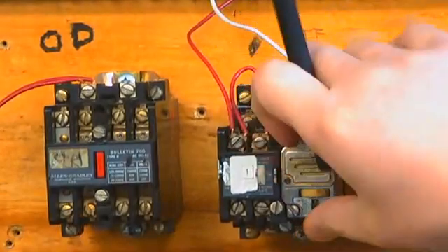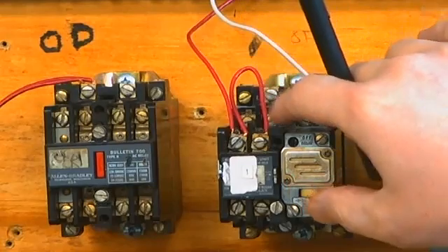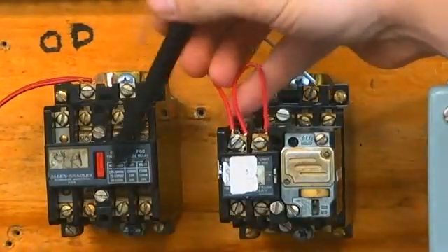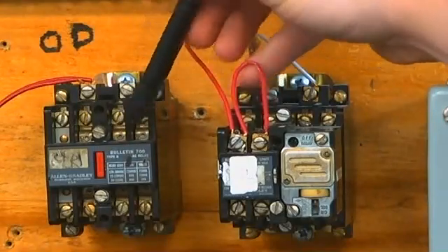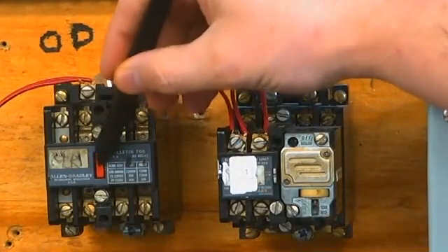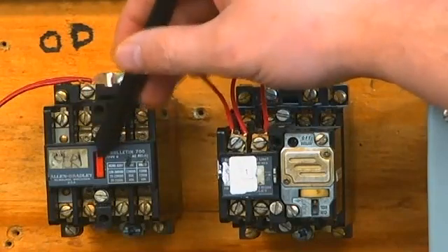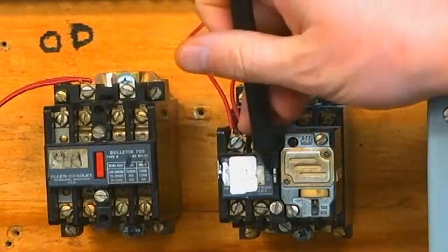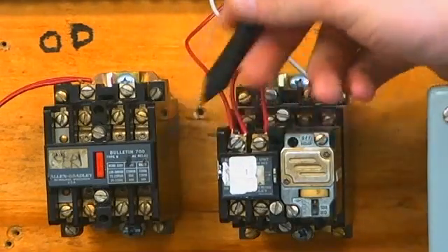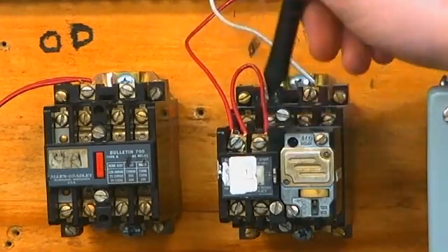I could take this thing off of here and show you that. Okay. If I take this timer off, what you're left with is this. And the timer operates, this little plunger here sits on this red indicator. So when that coil, the same coil that does the work here, gets energized and that pulls in, this plunger gets pulled in at the same time because there's a spring pushing back on it. So whenever the coil gets energized for the relay, the timer starts doing its thing.